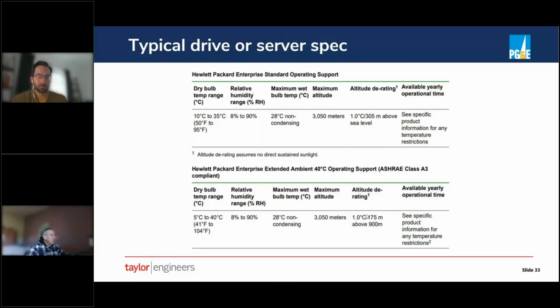If you look at the servers themselves, they often will publish their criteria. And so this is from an HP server many years ago that said it can operate between 50 and 95, and that the humidity can be anywhere from 8% to 90%. And then they actually provided an option in this case for an ASHRAE class A3. Remember those classes? It had an even wider dry bulb range. And so, at least from our experience, what the computers are saying they can operate to is generally quite a bit wider than what the ASHRAE range is limited to.